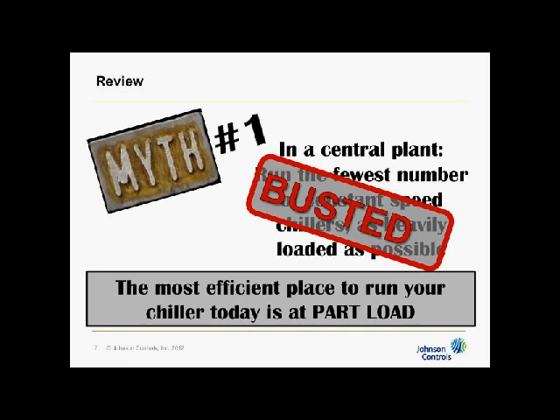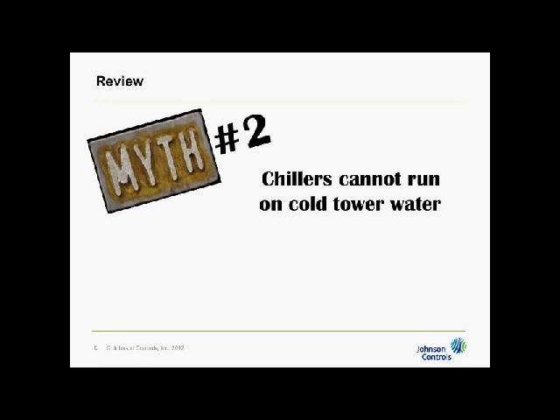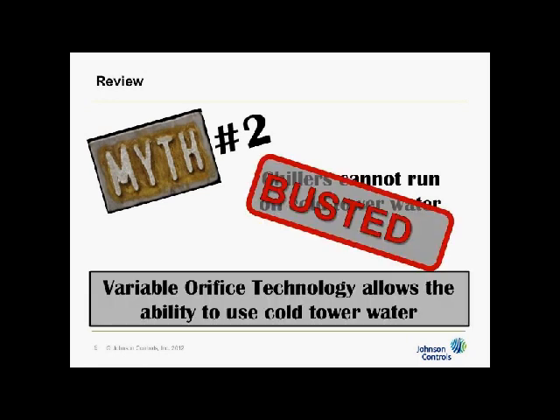The most efficient place to run chillers today is at part load. Myth number 2 was that chillers cannot run on cold tower water. That one was busted because if your chiller is designed to be able to handle oil eduction to get oil back to the sump, if your chiller is designed to be able to handle heavy loads or full load with minimum condenser water, that's usually done with a variable orifice, then you can definitely handle low tower water and not only save energy but operate consistently and stably.